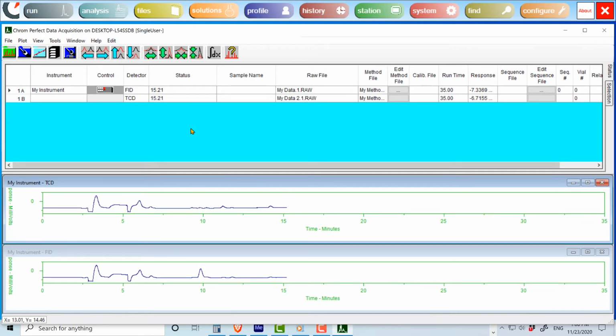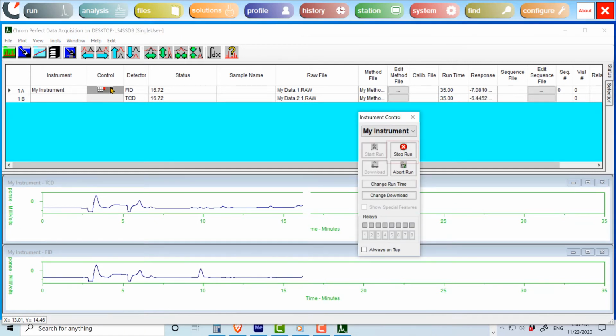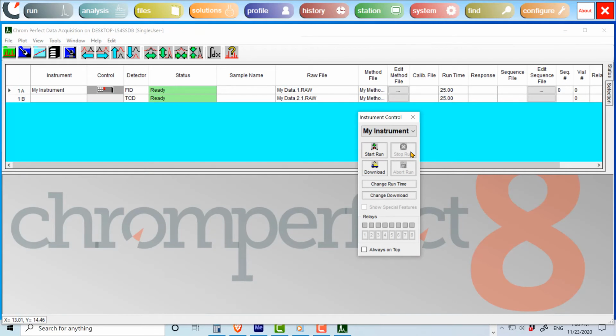When the runtime elapses, the plots will vanish and the cycle number will increment. Alternatively, you can stop the run early by pressing the Stop button on the Instrument Control dialog box. This will save the current run and create your data file. Or if Abort is pressed, the run will terminate, but data will be discarded and no file will be saved. When the status returns to Ready, this is your indication that Chromperfect is ready for the next run. Sometimes the instrument may take a while longer, so instrument status may change to GC not ready, but eventually it will change to Ready and you can make the next injection.